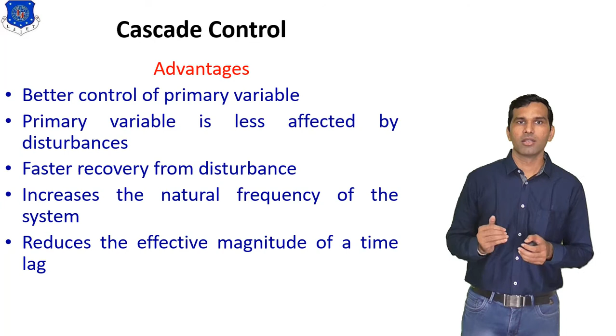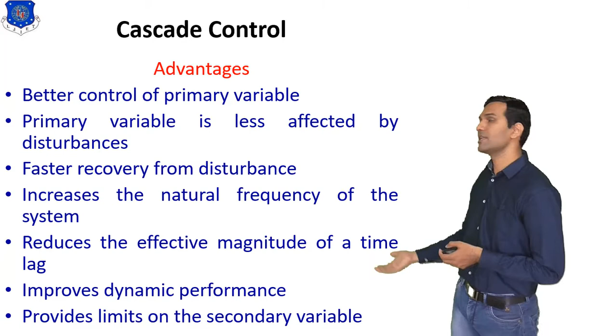Then it reduces the effect of the magnitude of time lag. That means we can reduce the control lag, or reduce the magnitude or the time of the time lag. So these are the advantages. The next advantage is improved dynamic performance. The cascade control system improves the dynamic performance of the system. And the last one is that it provides a limit on the secondary variable. So these are the advantages of the cascade control system.